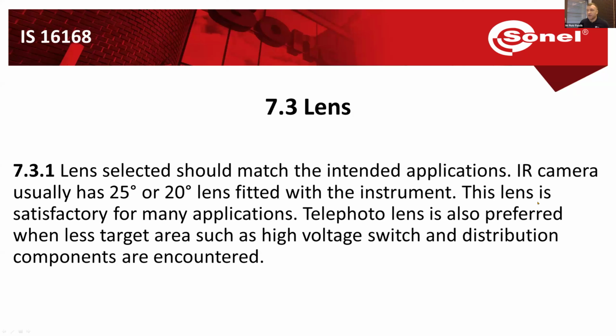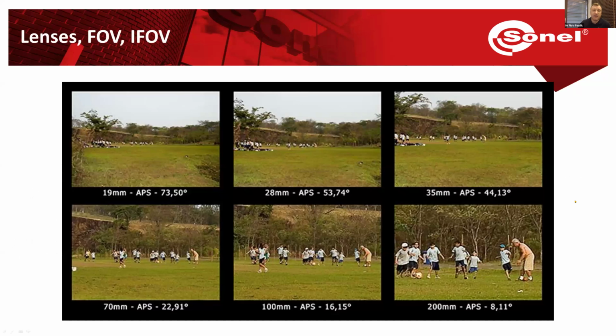Okay, the next part is the lenses. Here the standard says that typically infrared cameras use 20 or 25 degree lenses, which are fitted within the instrument. But sometimes we may want to use different lenses, like telephoto lenses or maybe wide-angle lenses. To give you the idea, here I have visual pictures. We have a 22, nearly 23 degree lens in the bottom left-hand corner. And all of these pictures were taken from the same spot with different types of lenses.